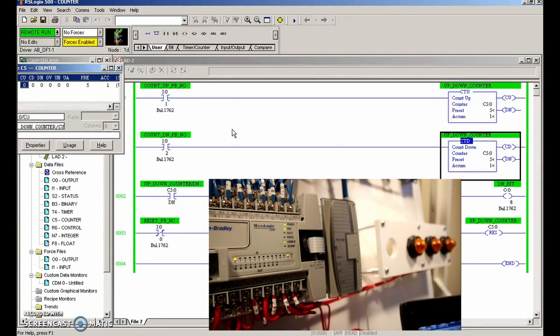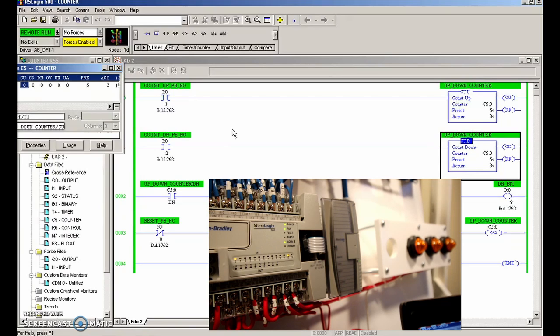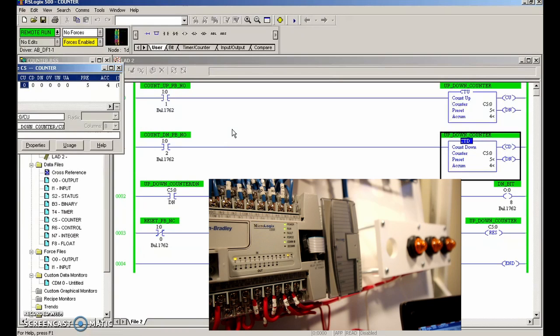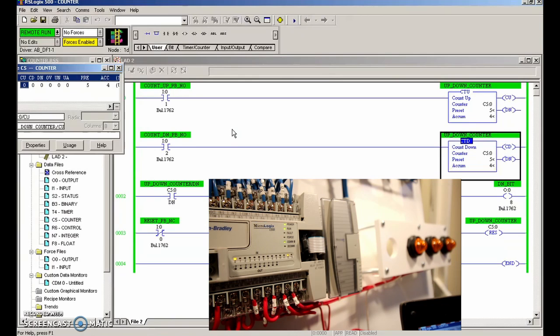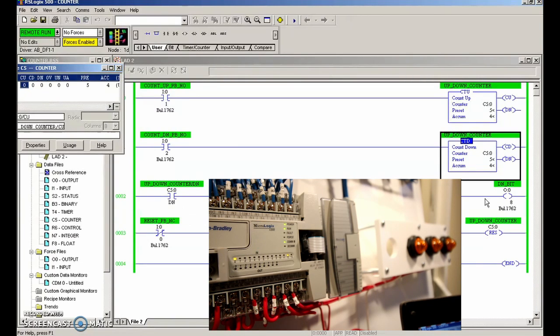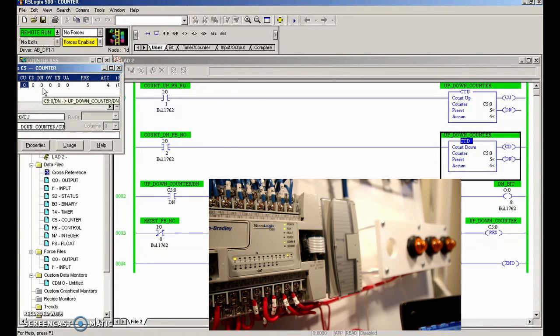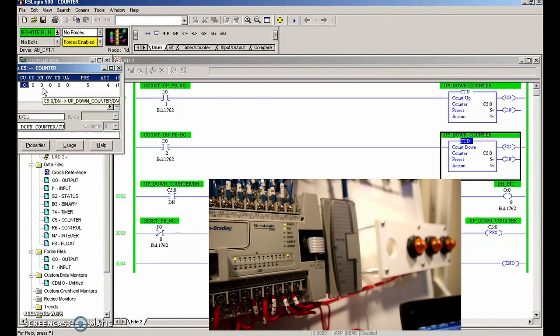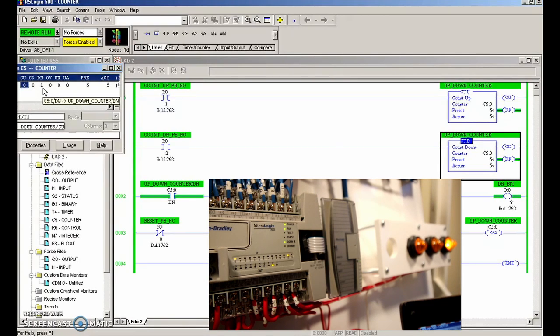Every time that this instruction in line with the up counter is true, we're going to increment up by one. So one, two, three, four—you can see that it retains the value even when I let go of the push button. When the accumulated equals the preset value, then the done bit will set. This value will go to a one. We're examining that it's a one, so this light will also turn on. There it comes—beautiful. So the done bit has set.